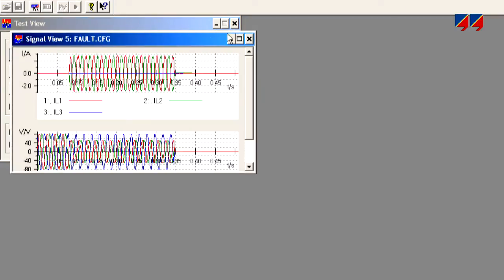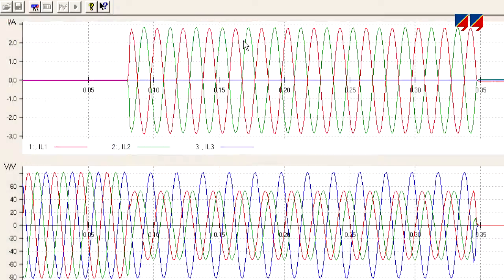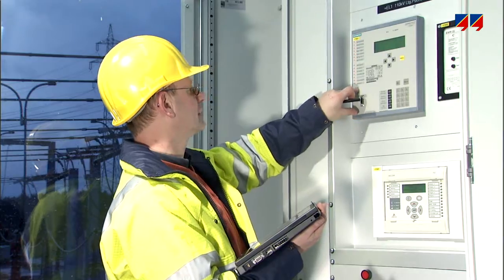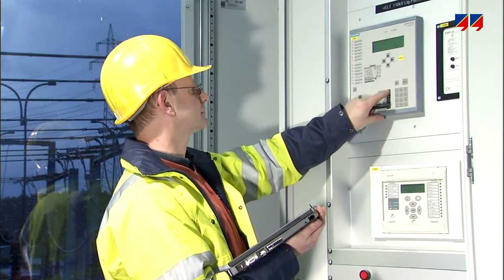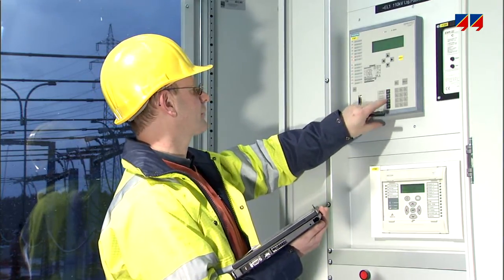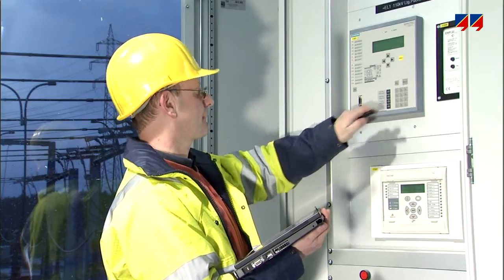The CMC also allows the recording and playback of fault records in COMTRADE format. In this way, the performance of protection systems in the presence of actual fault conditions can be determined. Today's relays offer a wide range of additional functions in addition to the main protection.